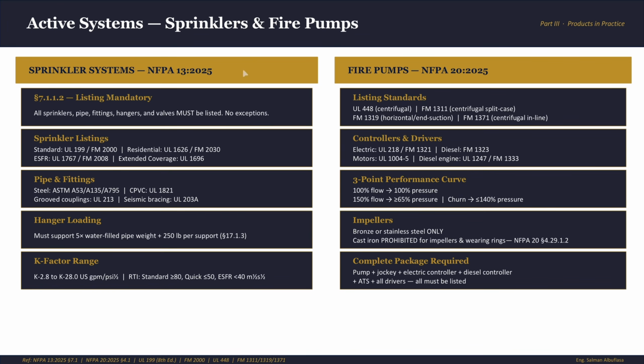Anyways, the sprinkler system is only as good as the water behind it, and the water is only as good as the fire pump behind it. The fire pump is what matters here. It's the heart of the system. If it doesn't deliver the required flow and pressure to the most demanding point in the network, the entire suppression system fails. NFPA 20 states the entire fire pump package must be listed. Not just the fire pump body, everything. The pump, the electric driver and its controller, the diesel driver and its controller, the automatic transfer switch or the ATS, each component individually listed, and then the complete assembled package verified together.